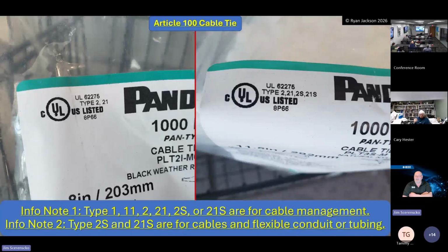The reason they put that in the code was because a lot of people were going down to the flea market buying a 55-gallon drum of cable ties that couldn't support anything, and they would just put them up in the ceiling and they had no tensile strength whatsoever. They also have to be listed for the type of plenum they're in, or if it's a fire rated, or if it's a plenum ceiling, plenum rated, fire rated, whatever they are.